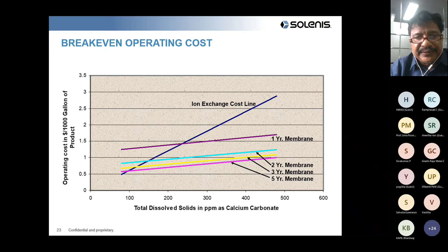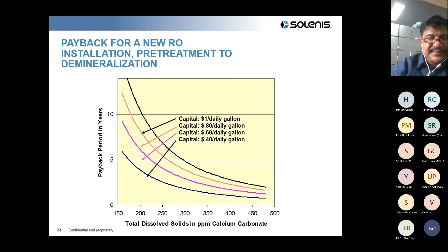So this is where I talked about the capex and the opex, wherein you have a payback period. For example, I have a DM plant of capacity 10 meter cube per hour requirement. The cost of the plant is only 10 lakhs. The 10 meter cube per hour RO plant will cost about 40 lakhs. But the operating cost of the DM plant will be say 25 rupees per cubic meter, and the operating cost of the RO plant is 8 rupees per cubic meter. Then we work out the payback, and we'll find that the payback is even less than 2.5 years. That is where I told you that we look at the capex and the opex as far as the calculations are concerned.